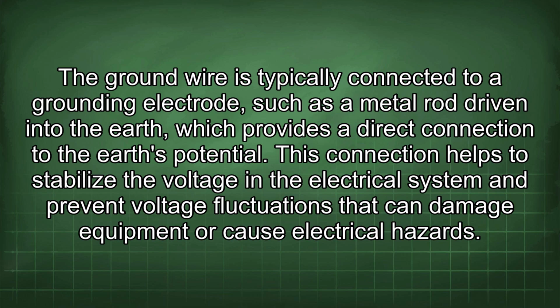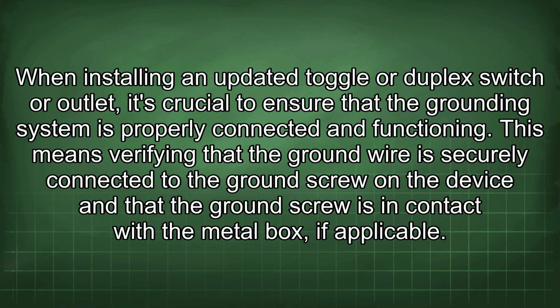This connection helps to stabilize the voltage in the electrical system and prevent voltage fluctuations that can damage equipment or cause electrical hazards. When installing an updated toggle or duplex switch or outlet, it's crucial to ensure that the grounding system is properly connected and functioning. This means verifying that the ground wire is securely connected to the ground screw on the device and that the ground screw is in contact with the metal box, if applicable.